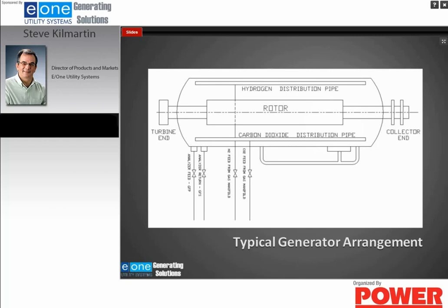During the purging process, you're going to want to have the analyzer taking its sample from a different location, and I'm going to explain this in a minute. But when you come out of an outage, this generator is filled with air. And you don't want to put hydrogen in the generator when there's air in the generator, so we want to use an inert gas to remove the air. In this case, we're going to talk about using carbon dioxide as a purge gas. There are manufacturers and there are utilities that will use a different gas or different gases, but in my explanation, we're going to use carbon dioxide.